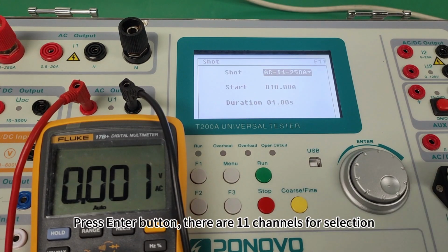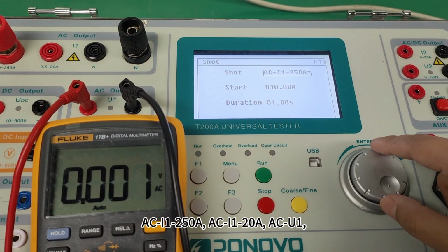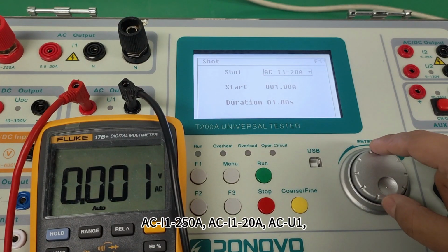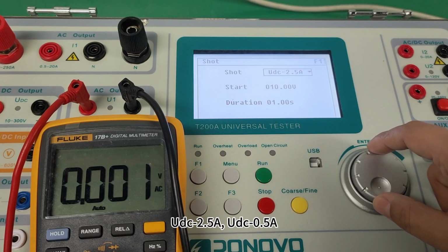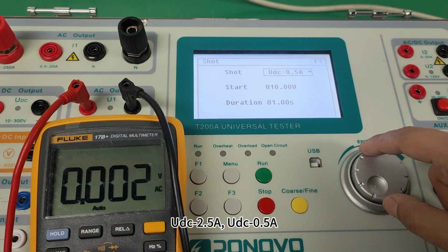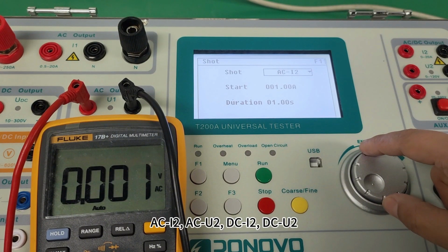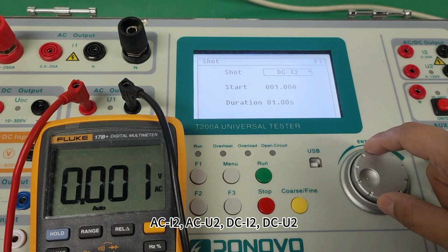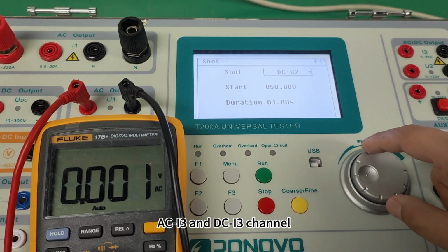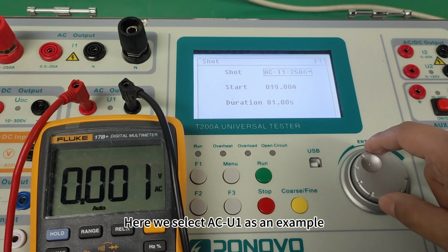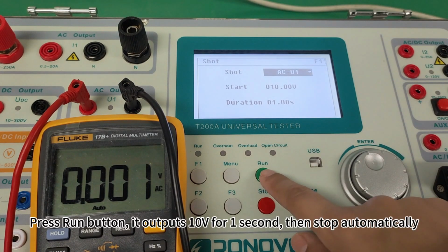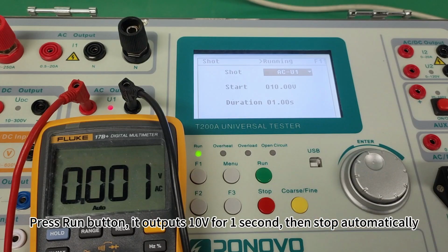Press enter button. There are 11 channels for selection: ACI1 250 amperes, ACI1 20 amperes, ACU1, UDC 2.5 amperes, UDC 0.5 ampere, ACI2, ACU2, DCI2, DCU2, ACI3 and DCI3 channel. Here we select ACU1 as an example. Press run button. It outputs 10 volts for 1 second, then stop automatically.